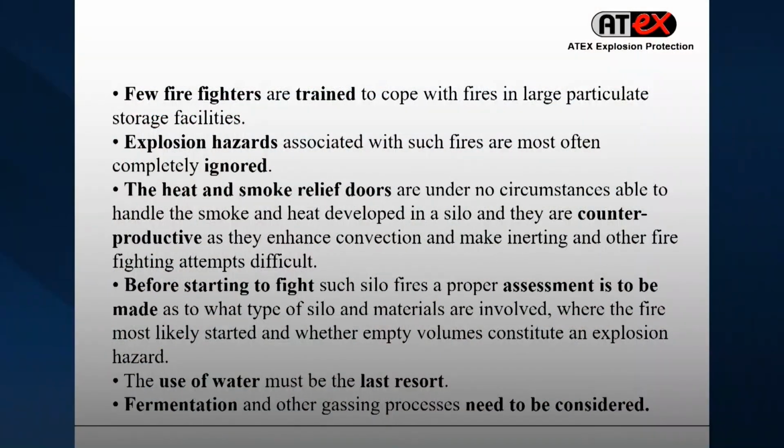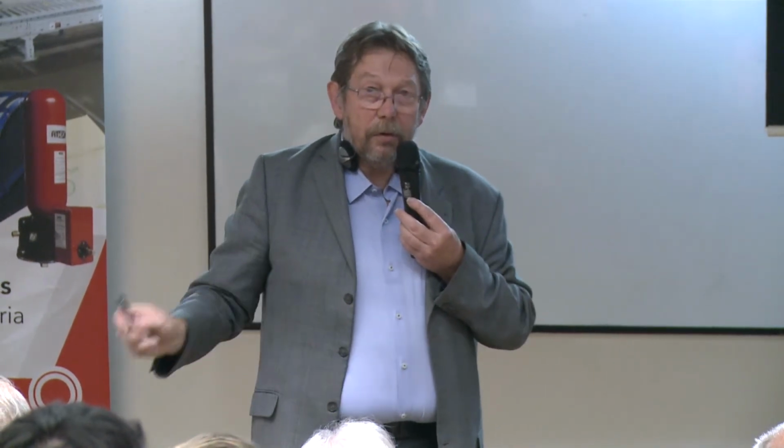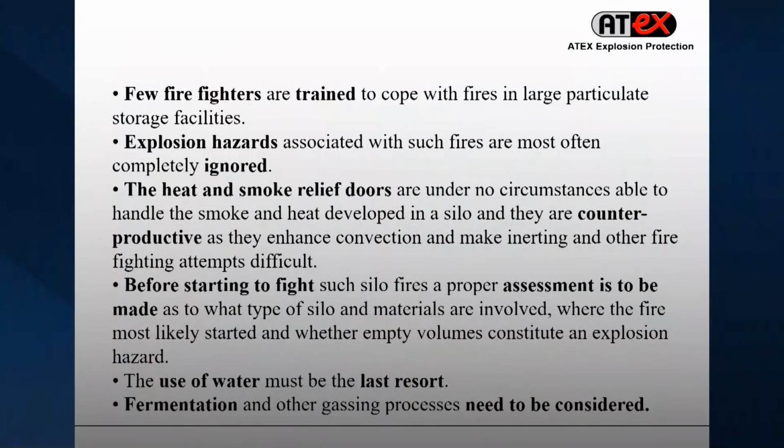Firefighters need to be trained, and the heat and smoke relief doors, which used to be a law in at least Germany, that a big silo needed to have escapes. They caused a problem because we got a big draft, and it enhanced the fire, and it didn't help at all. Therefore, now we don't need those doors there anymore.